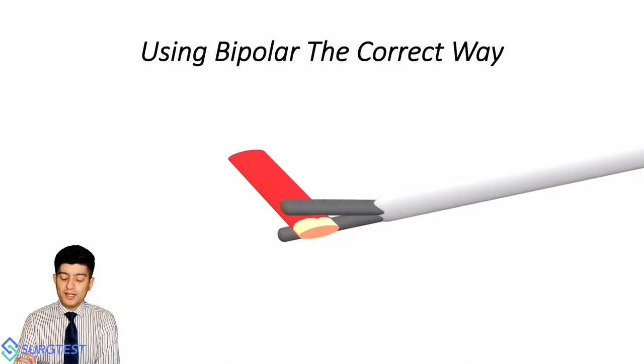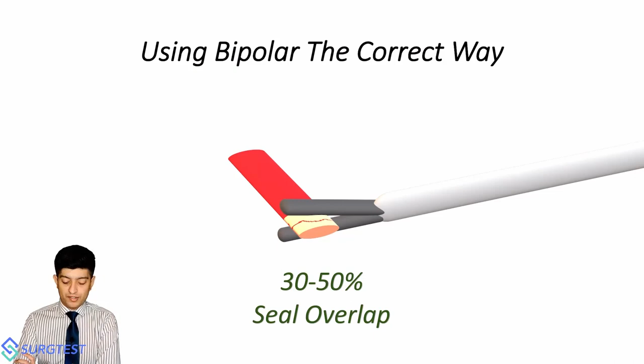What you want to do is, once you have created a nice seal, you want to move slightly away from that area, having an overlap of 30 to 50% and then refiring the bipolar device there. So you want this around 30-50% overlap to improve the strength of your seal, but not jeopardizing the tissues that you're trying to achieve hemostasis in.